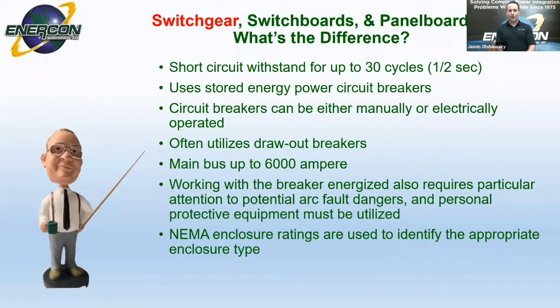Breakers can either be manually or electrically operated, and often draw-out type breakers are preferred for ease of replacement. And we'll get into more of that as we go on here. Main bus is typically up to 6,000 amp. That's really where we're going to top out there for main bus.